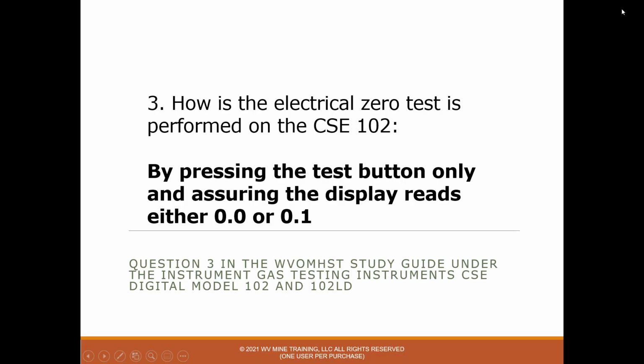Question 3, how is the electrical zero test performed on the 102? And that is by pressing the test button only and ensuring the display reads either 0.0 or 0.1. So electrical zero means that it gives you the correct answer. If you're out in your bathhouse at your mine and you have a CSE 102 and you press the test button, there's no methane there. So it should display either 0.0 or they will allow a 0.1 reading.